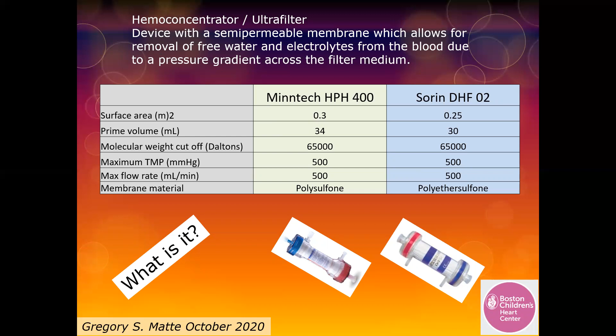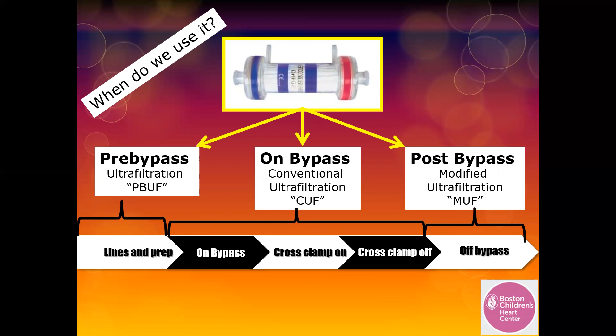And that universal use is because the hemoconcentrator can be used during all of the distinct phases of cardiopulmonary bypass. Before bypass with pre-bypass ultrafiltration, while on bypass with conventional ultrafiltration, and of course after bypass with modified ultrafiltration. We do not have time to discuss a literature review of pre-bypass, conventional, and modified ultrafiltration, but I also do not think it's necessary. Intuitively, it makes sense to optimize the pump blood whenever possible and to return as much patient whole blood to the patient as possible after a surgical case. And that speaks to why we are using ultrafiltration during the distinct phases of bypass.